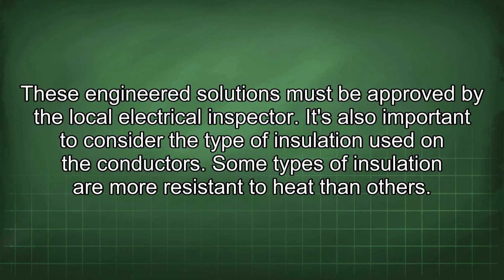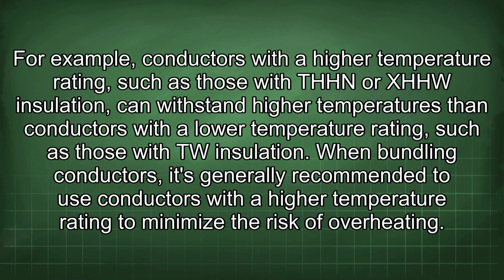It's also important to consider the type of insulation used on the conductors. Some types of insulation are more resistant to heat than others. For example, conductors with a high temperature rating, such as those with THHN or XHHW insulation, can withstand higher temperatures than conductors with a low temperature rating, such as those with TW insulation. When bundling conductors, it's generally recommended to use conductors with a higher temperature rating to minimize the risk of overheating.